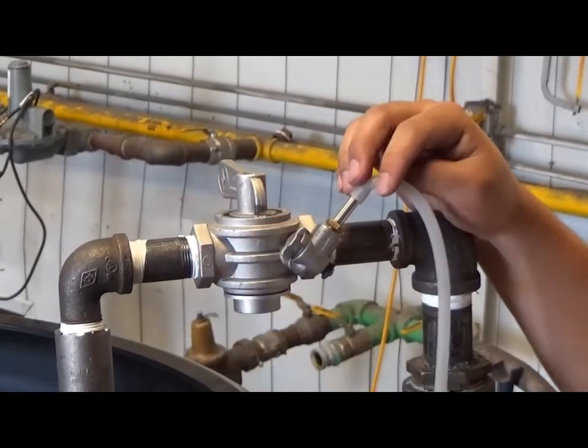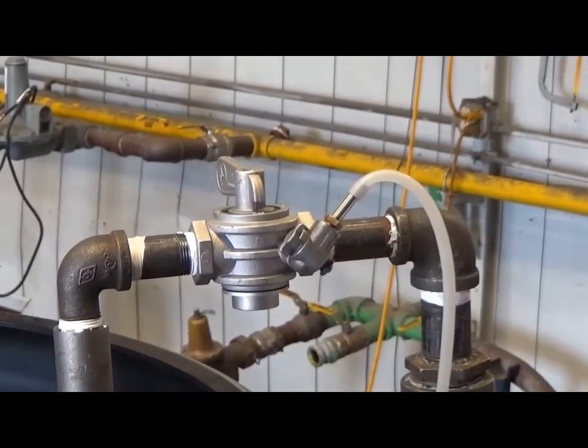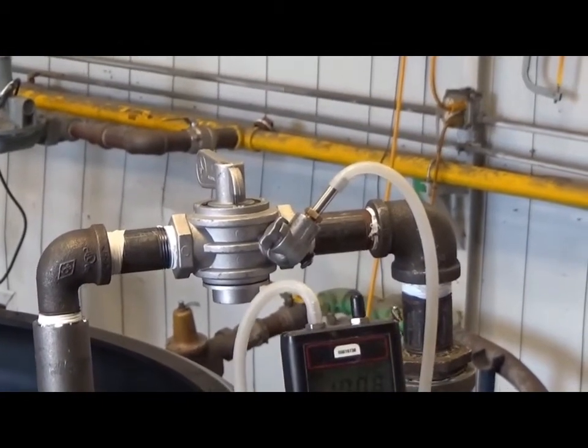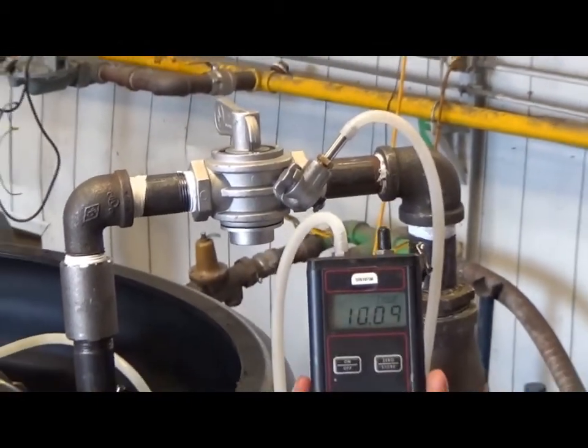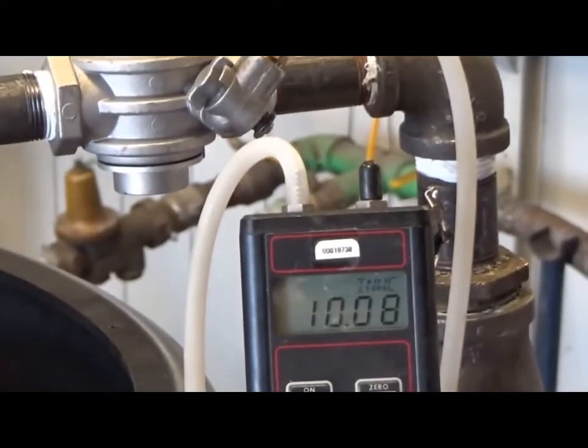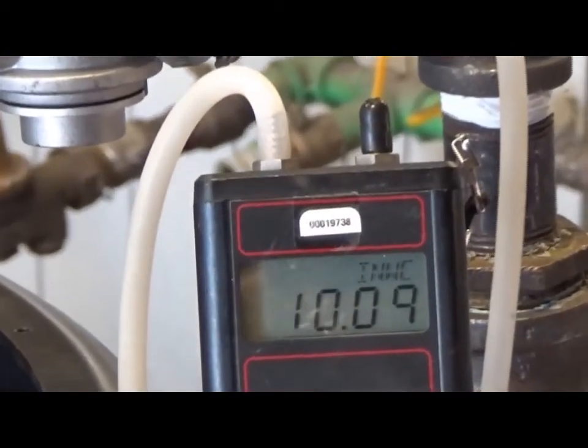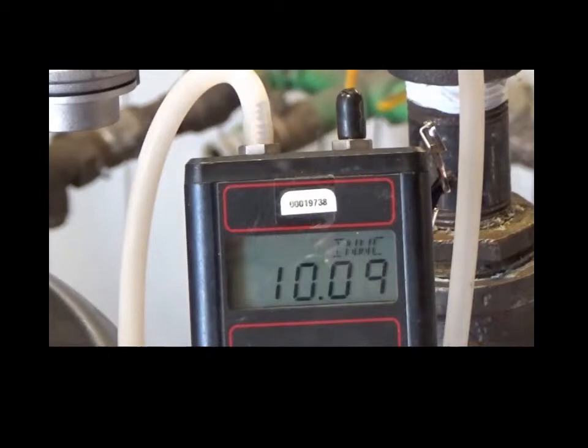With the burner firing, measure the flow gas pressure at the beginning of the gas train. If the inlet flow gas pressure is equal to or greater than 3.5 inches water column, continue with the startup. If the inlet flow pressure drops below the minimum required, a supply gas volume or piping problem may exist and must be corrected before the startup can continue.